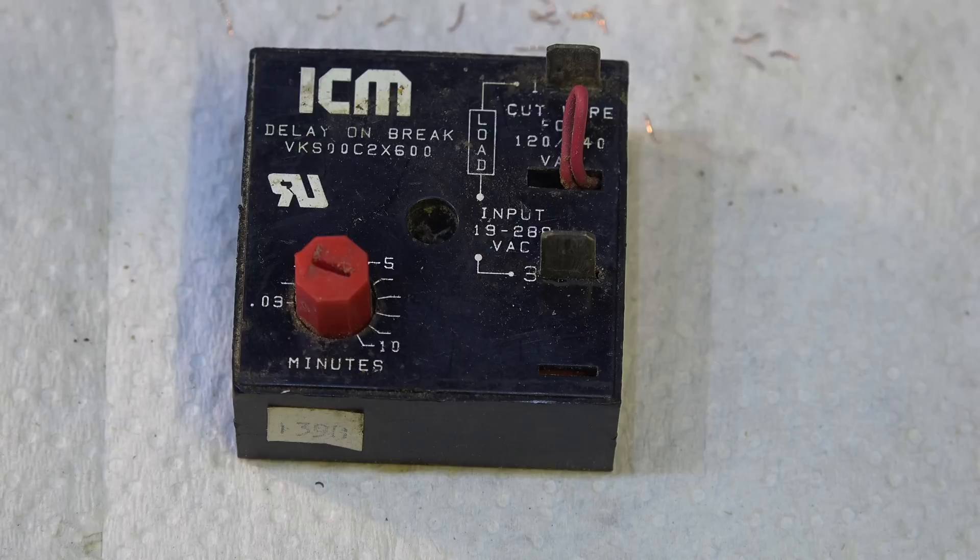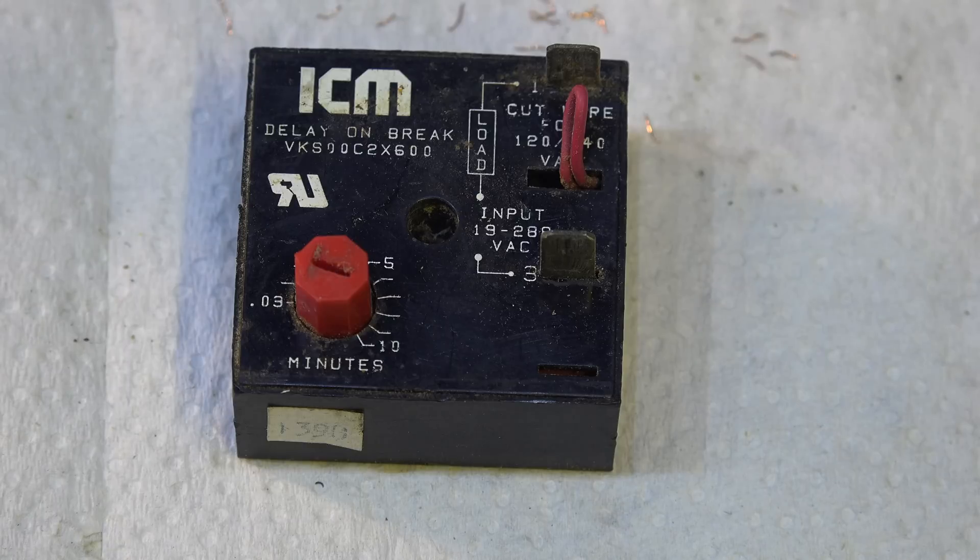What are you using it for? In the HVAC industry, we use compressors. Compressors, when they shut off, have a high pressure on the high side and a low pressure on the low side. If they are not hard to start compressors and we try to start them immediately after we've shut them off, they oftentimes won't start.